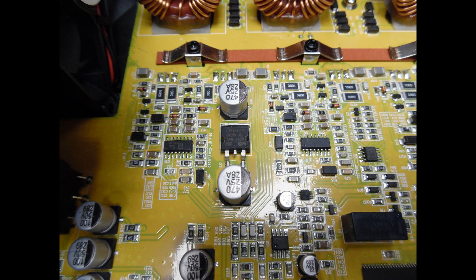Now all these power supplies have a single protection circuit, but that protection circuit is made up of other measurement devices. Within the power supply design there are what we call comparators, which are integrated circuits, normally dual comparators. You'll have a reference input on one side of the comparator, and it monitors the input on the other side, then provides an output.